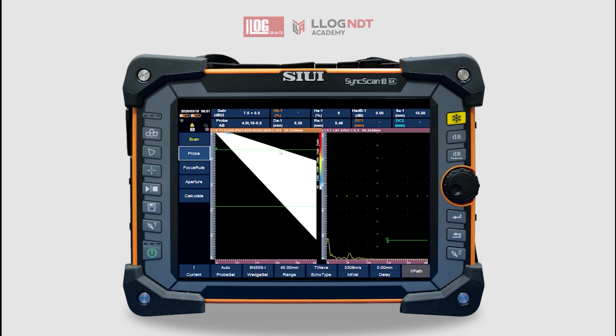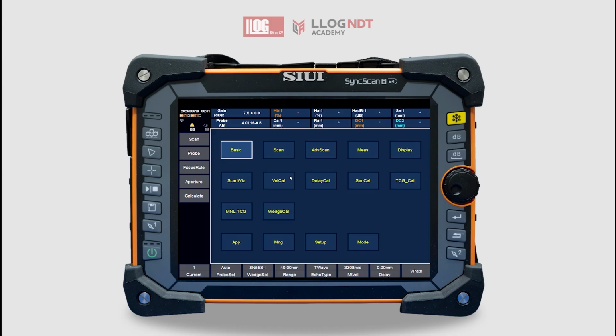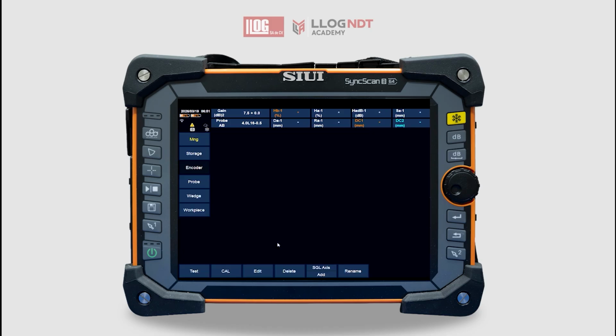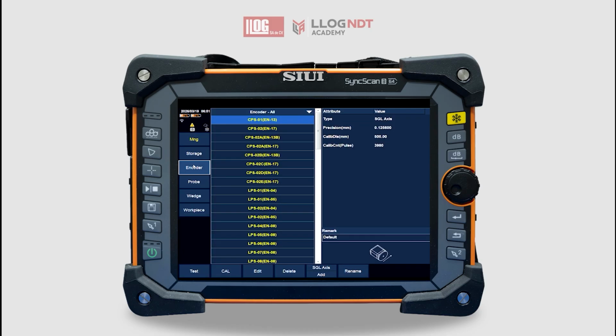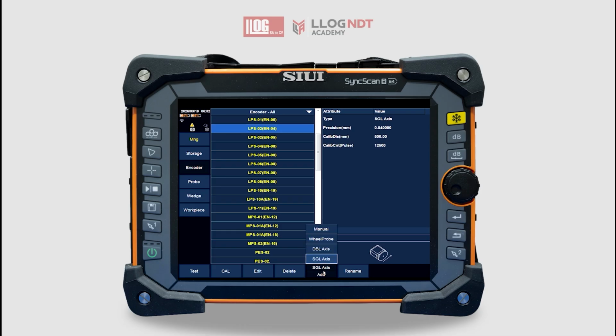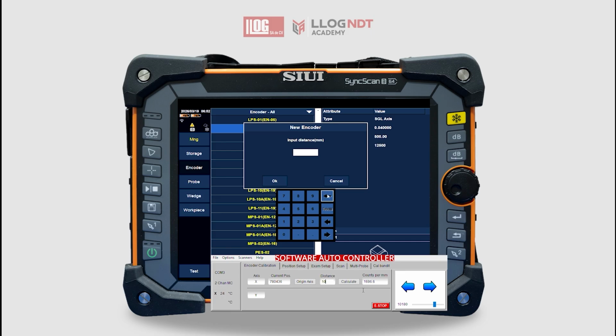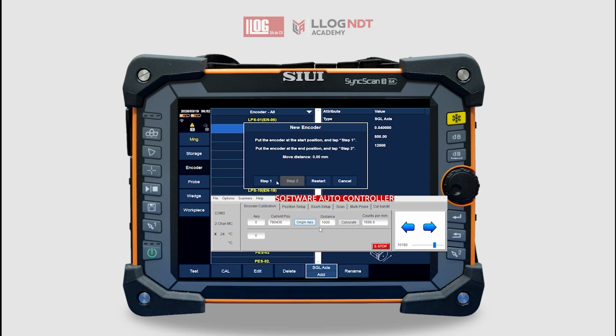For encoder calibration, select the model on the instrument in the Manager menu. In the encoder section, choose the model based on the encoder characteristics being used. For this example, select the LPS02EN04 model. Create a new setup and enter the reference travel distance, 1,000 millimeters. The instrument will prompt you to place the encoder at the starting position, that is, at the 0 reference.